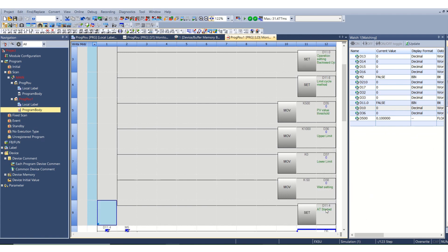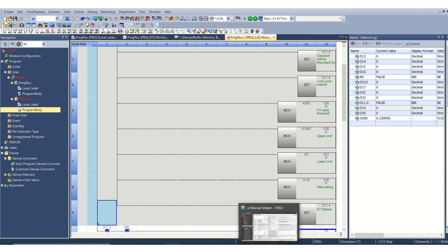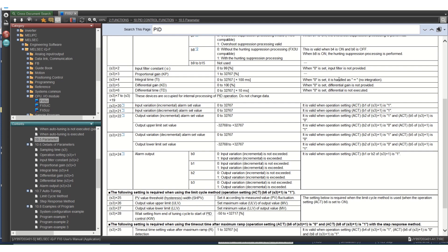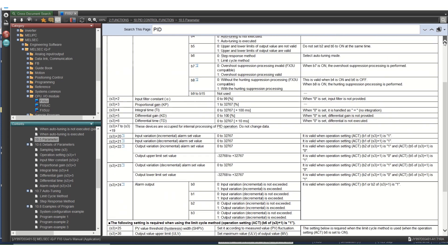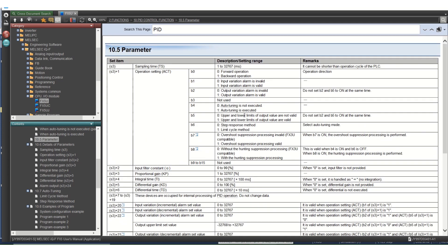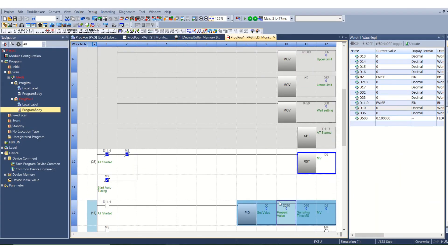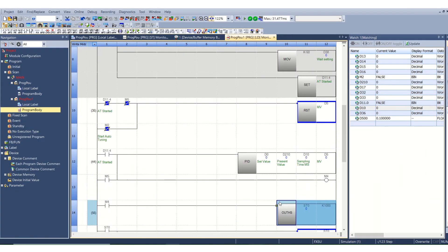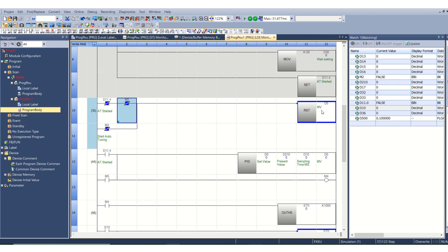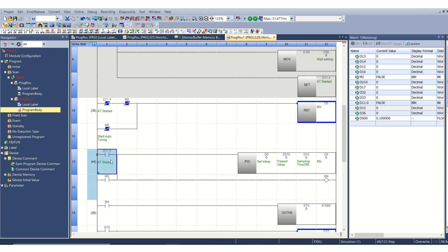Now, D11.4 is for autotuning started. This 4 bit indicates autotune is executed. This is the initial work. Now if you use M5, M5 is used as a bit and I am resetting the MV manipulated value, that is output of PID function, to 0 initially.